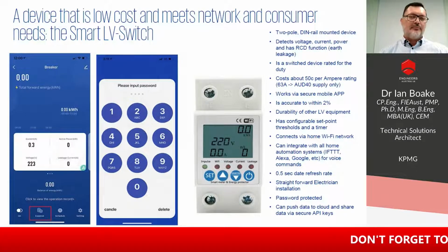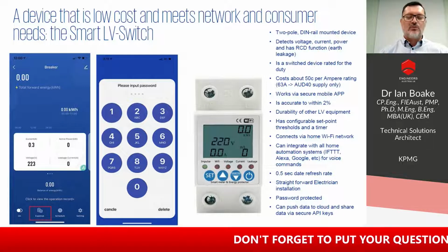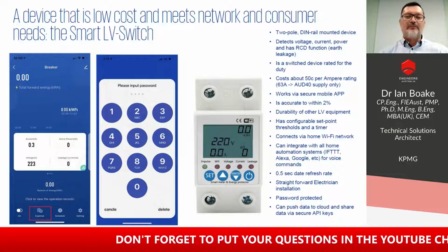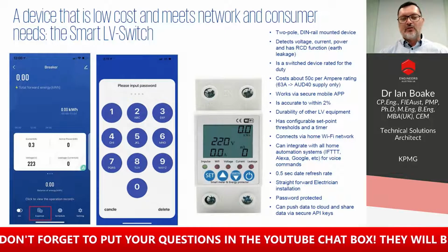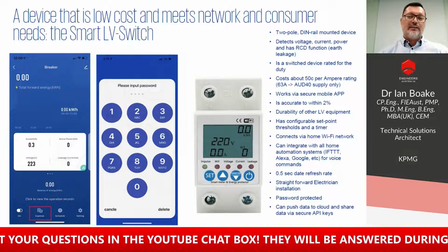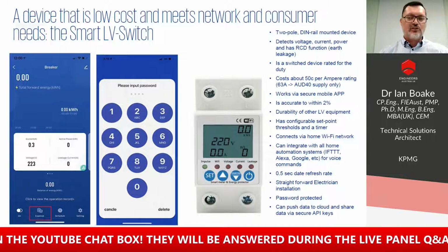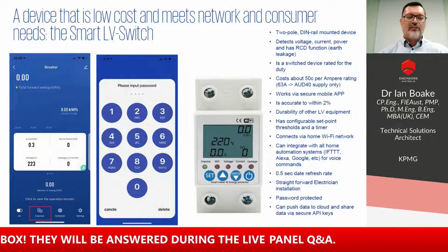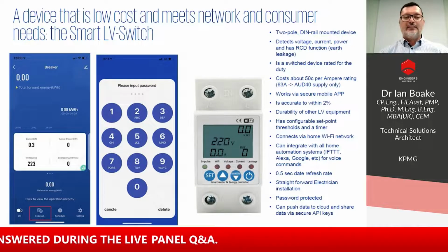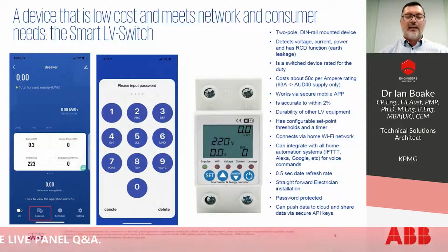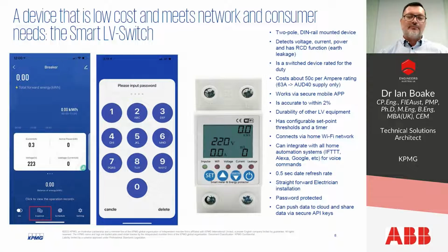So here's a device that I have come across. It's a low voltage device. What's quite important about it is it's at a price point of about 50 cents per ampere, so fairly inexpensive. It has voltage, power flows, current. It even offers an earth leakage or residual current device function. And via a smartphone app, which you see on the left-hand side there, and a password, you can access this device, switch it on through timers, and integrate it with third-party devices. Now, that is typically at no cost to the consumer because it's low volumes of data. And if this data is then made available to DNSPs through some sort of third-party API key, that then provides them zero-cost information right at the fringe of the network.